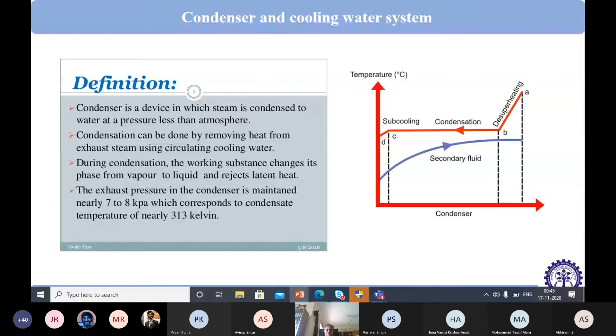So this figure is important, but this is a generalized figure that when superheated steam is coming, then it is condensing and then it is being subcooled. When steam comes from the turbine, generally it is wet steam. So it will start somewhere from here, and there could be some sort of marginal subcooling. And this diagram, where there is desuperheating, condensation and subcooling, is valid, or rather relevant, for feed water heaters, particularly high pressure feed water heaters. So steam is extracted at superheated condition, then it is desuperheated, then condensation takes place, and then marginal subcooling takes place.